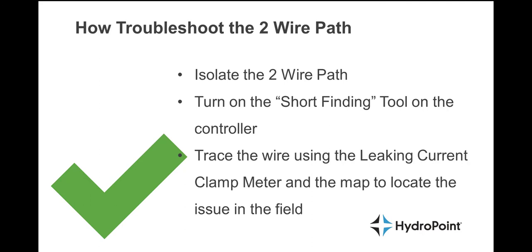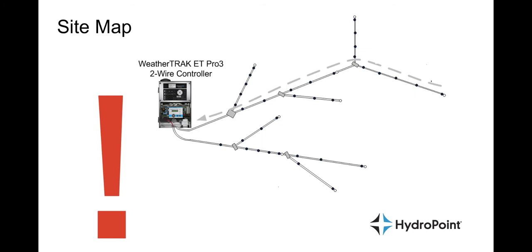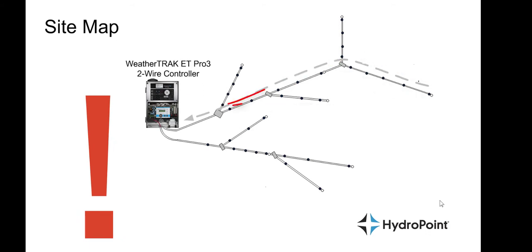When I turn on the short finding mode on the 2-Wire interface, it sends a test signal down the path and displays the total milliamp reading coming back to the controller from the farthest ends. So what you see at the controller is the total milliamp reading for the entire 2-Wire path. We turn on short finding mode, get a sample reading at the controller as a baseline — and maybe here at the controller we get a hundred milliamps, something way out of the ordinary for a 2-Wire path. My biggest controllers operate at about 50 milliamps, so anything outside of the norm is what we are looking for.